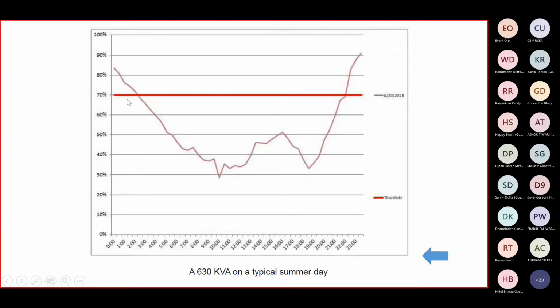If we set a threshold of say 70% - this may vary from utility to utility, but for us 70% is the threshold, beyond which the planning starts to augment or upgrade a particular line or asset - you can see that in this transformer, beyond 70%, there are only a few instances, say from late night, from 20 hours to around 2 in the morning, where it crosses the threshold line. The rest of the entire day it is under the threshold line, below 70% of the rated capacity of 630.